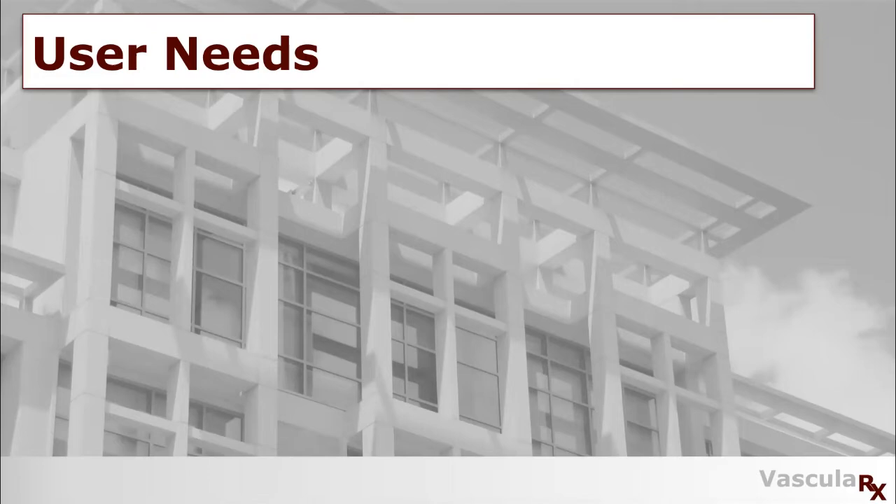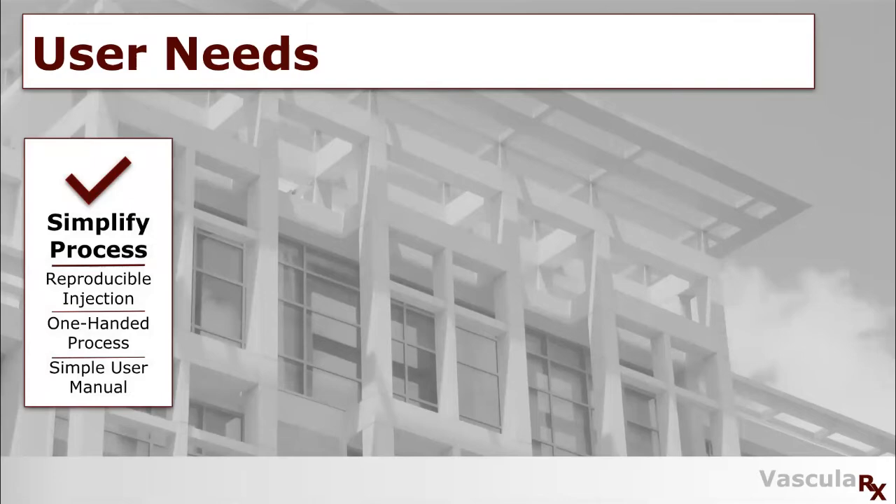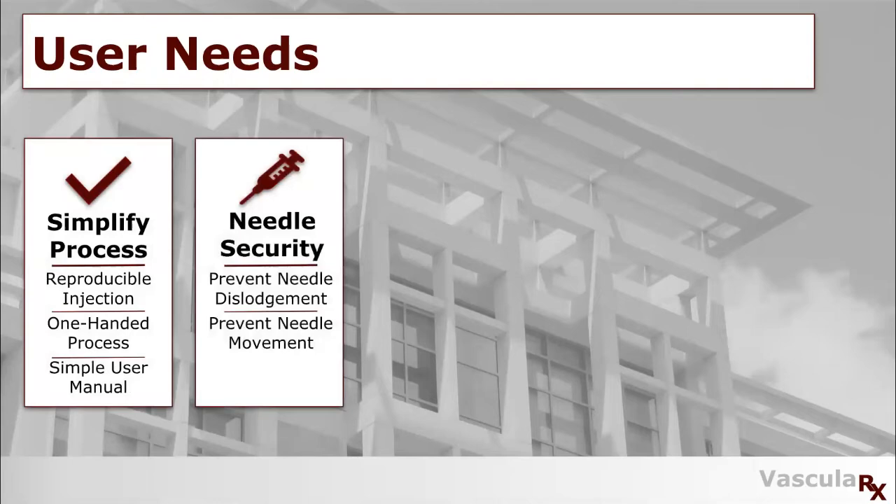The first user need was to simplify the process. For this, we wanted to focus on having a reproducible injection and making it a one-handed process so patients could cannulate themselves. Next, we looked at needle security — specifically to prevent needle dislodgement during hemodialysis and to prevent uncomfortable needle movement.